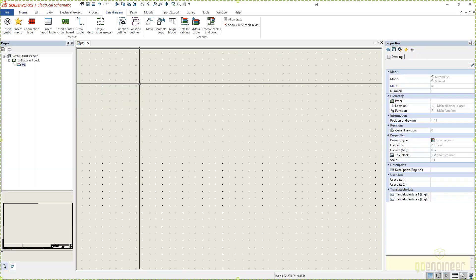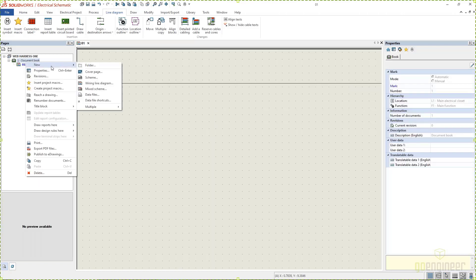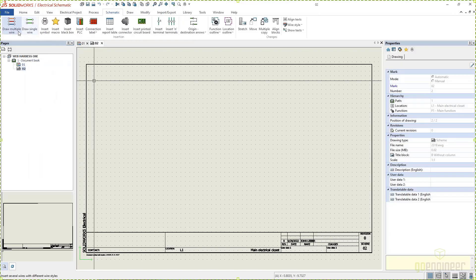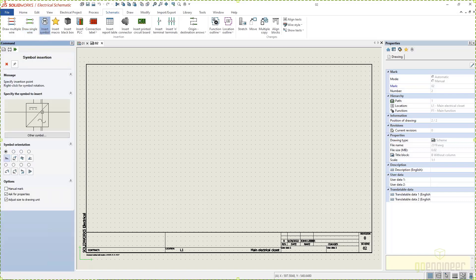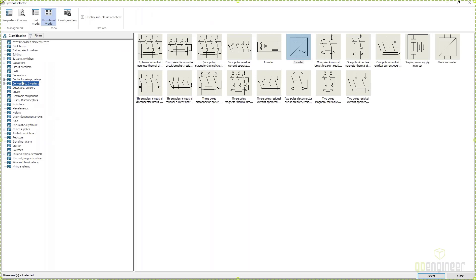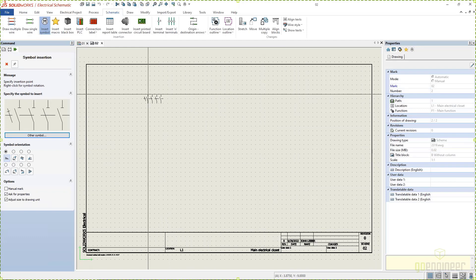But how does this work when we're talking about symbols for components in a schematic where we're going to do multi-wires? There are two things we have to think about. Number one, we're going to have our wires. When we go to draw the wires — so if I right-click here and say new scheme this time — the defaults out of the box settings inside of SOLIDWORKS, all the symbols that SOLIDWORKS provides are spaced off of 0.25 inches or quarter-inch spacing. So if I come in here and insert any symbol from these libraries, the cursor is always going to be at position one — pin one for SOLIDWORKS-provided symbols.